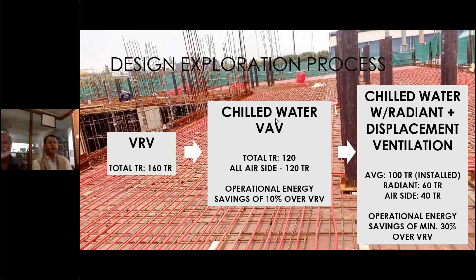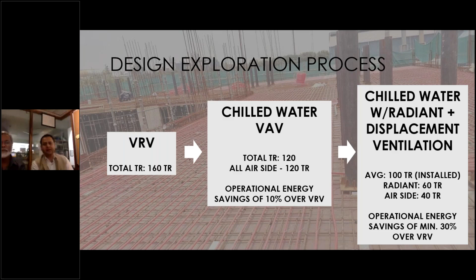And this is how we laid the foundation that this is the right system and this is how we wanted to go. So the chiller that we have planned is a standard, but a highly efficient chiller, whose coefficients of performance and part load values were normally higher than conventional ones. The low side system consists of a standard VAV system, the AHU system that takes care of the air side, but air is only provided equivalent to the fresh air required in the spaces, plus the latent load, because when we provide radiant cooling, the sensible load is normally taken care of by the radiant cooling.